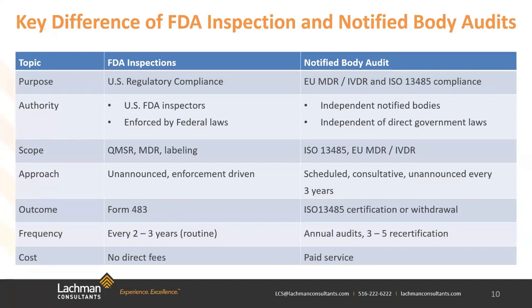Now, the frequency of these inspections: FDA usually comes every 2 to 3 years on a routine inspection for medical device class 2 and 3. As I mentioned earlier, if they're seeing something from the complaints and adverse reporting, or any other alerts that they receive, they could come in and do a for-cause inspection. For notified body audits, those are annual audits with a recertification every 3 to 5 years.